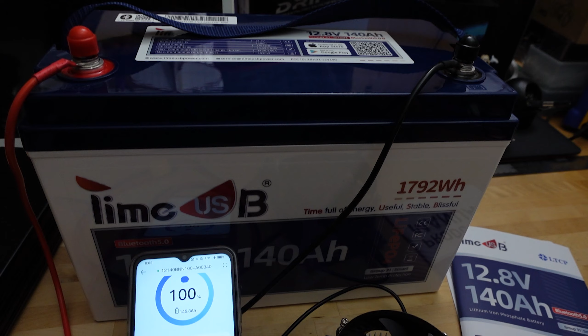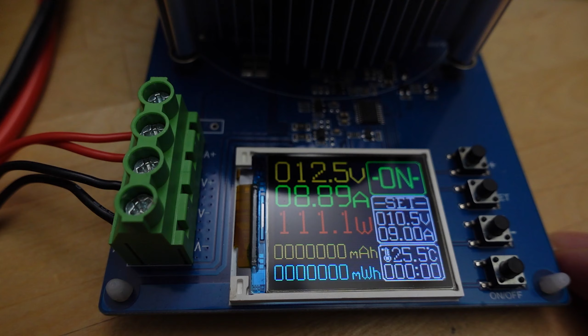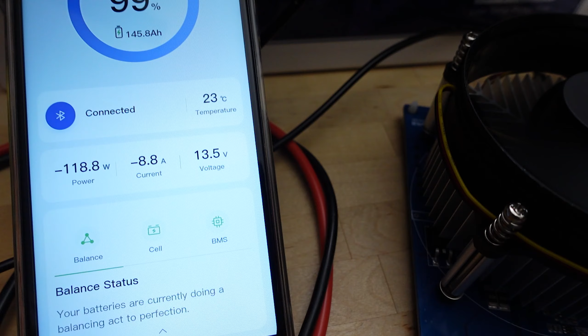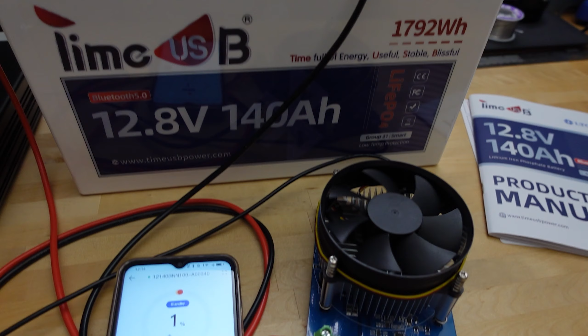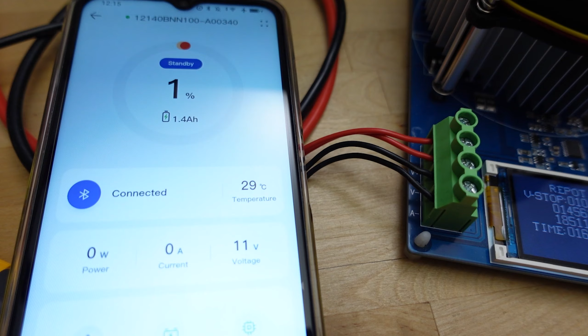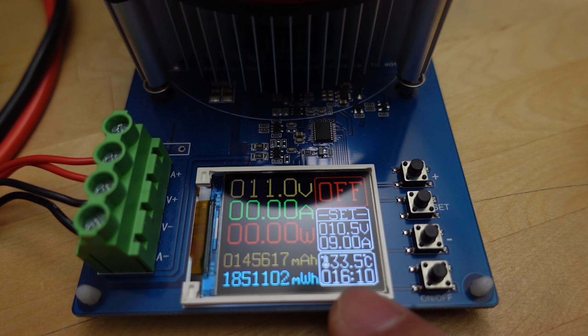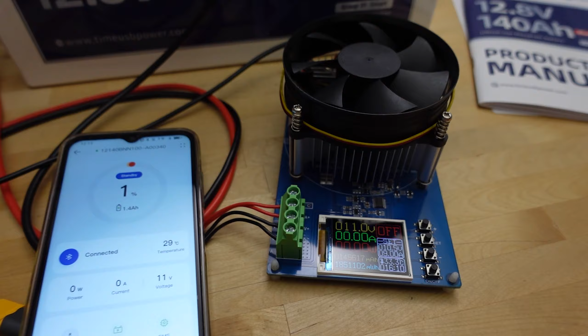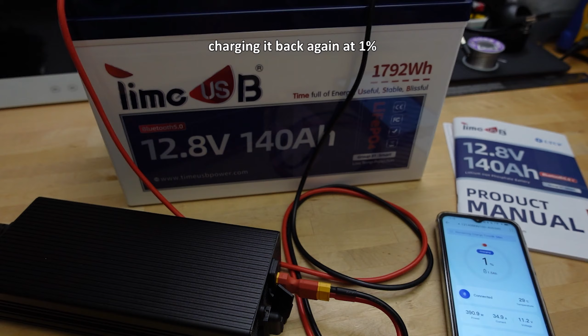I did do full capacity testing on this battery, wanted to see what I could draw out of it. So I charged it up to 100%, put it on my capacity meter, and ran it down at around 118 watts to about 10.5 volts, which is pretty much zero. It shut off at 10.5 volts with about 1% capacity left, and recovered to about 11 volts at rest. So there was a little bit of capacity left, maybe a little over 1 amp hour at 10.5 volts - I probably should have set it to 10 volts to get that last 1.1 amp hours. But even at 1% from 100%, I still got about 1,851 watt hours, and the battery is rated for 1,792 watt hours, so there was plenty of extra capacity.